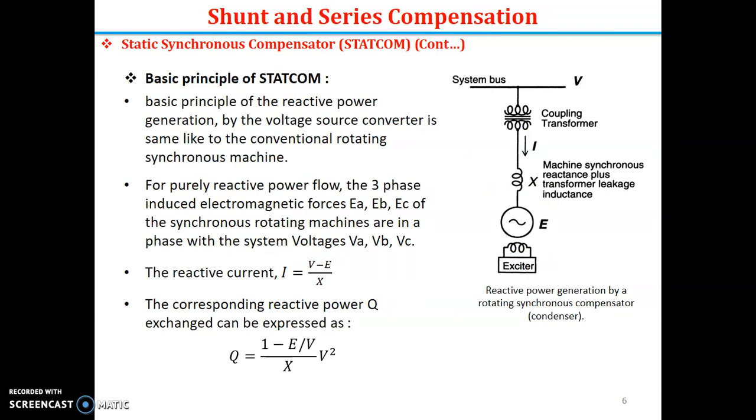Now let us come to the basic operating principle of the STATCOM, the reactive power generation by the voltage source converter, and it is the same as the conventional rotating synchronous machine. There is no difference in it, but it is a static solution instead of the previous dynamic or rotary solution. For purely reactive power flow, the three-phase induced electromagnetic forces EA, EB and EC of the synchronous rotating machines are in phase with the system voltages VA, VB and VC.